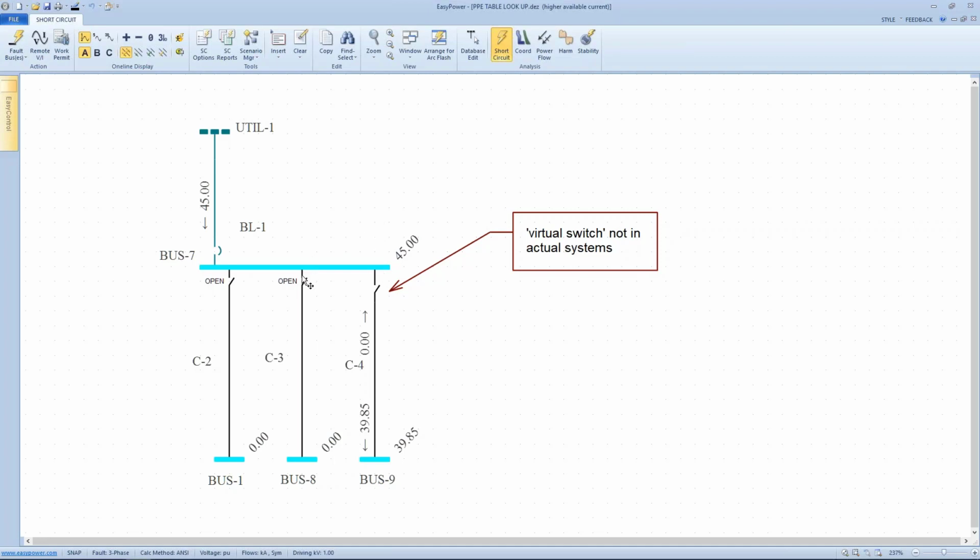Even if we look at other possible impedances, at that rate the worst case incident energy was still less than 1.2 calories. And at lower currents, it decreased enough that they were virtually not a concern.